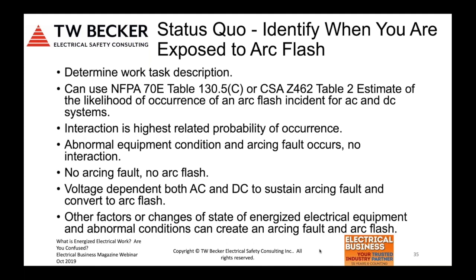So again, look to the right article or clause in Z462 and make sure you're clear on what an arc flash risk assessment is and what's required to be completed. So again, work task, let's say voltage measurement, 480 volts. Yep, at that voltage, we can sustain an arcing fault and arc flash. The worker's hands are going to go in and interact, but there's actually multiple discrete work tasks related to that job. We would go to CSA Z462 Table 2. We would find the work task description, and then based on condition of maintenance, it'll indicate the likelihood of occurrence of an arcing fault and arc flash as yes or no. So that's now the starting point as you go through the actual arc flash risk assessment, to reference this table as part of the process.